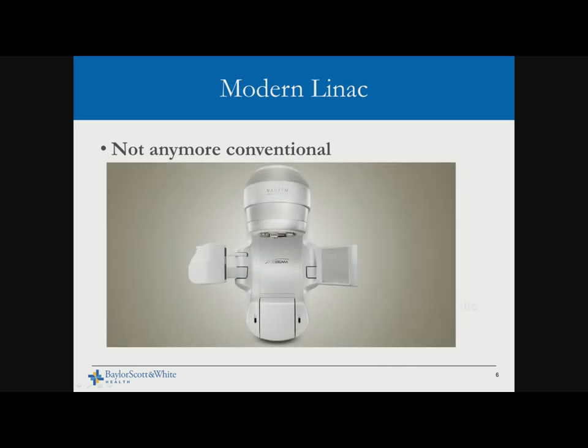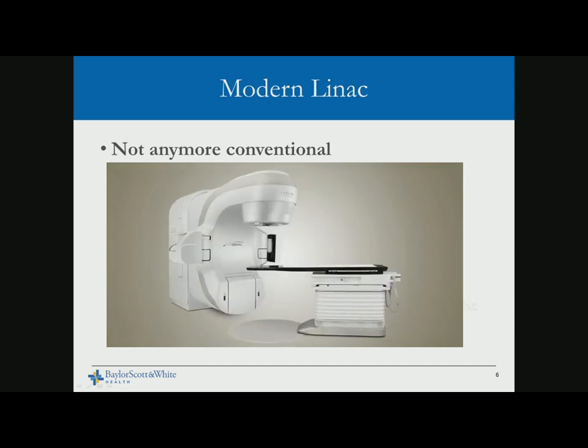Modern LINACs are not conventional anymore — if you look at the TrueBeam, it has a very sleek design. These machines now have imaging components, which didn't exist when TG45 was written in 1994. We also have 6D couches for radiosurgery machines and carbon fiber couches for RapidArc — we need criteria for accepting those. MLCs are becoming more sophisticated, with Elekta MLCs reaching speeds up to 5 cm per second.